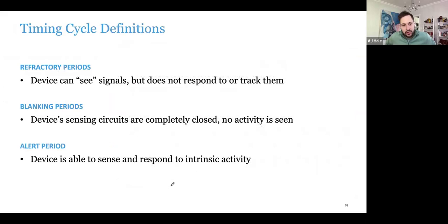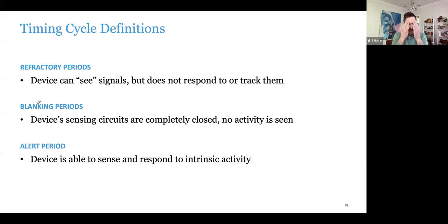So we'll jump right into timing cycles. We're going to go over the basic timing cycles. You have refractory periods — where the device can see the signals but does not respond to them. This would be your PVARP and your VREF. You have blanking periods — where the device completely has its eyes shut and is not paying attention at all. This would be your PVAB (postventricular atrial blanking) and the ventricular blanking period. And finally, alert period — the time when the device has its eyes completely open to respond to any kind of activity.